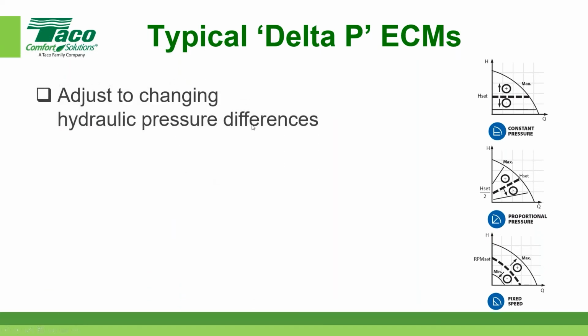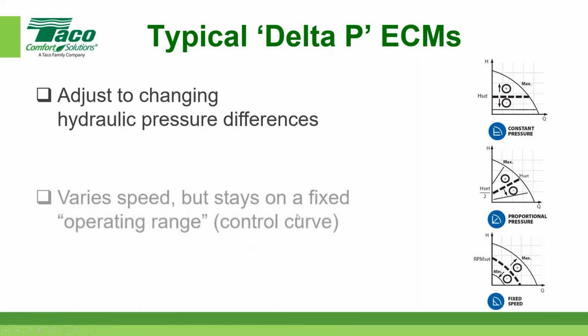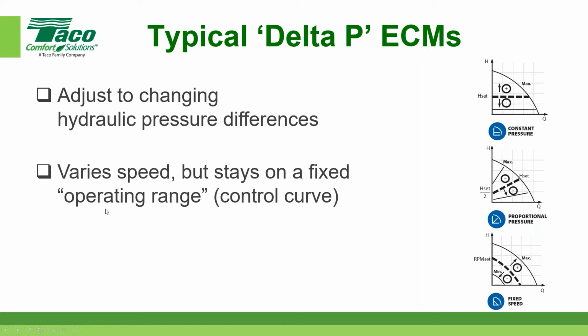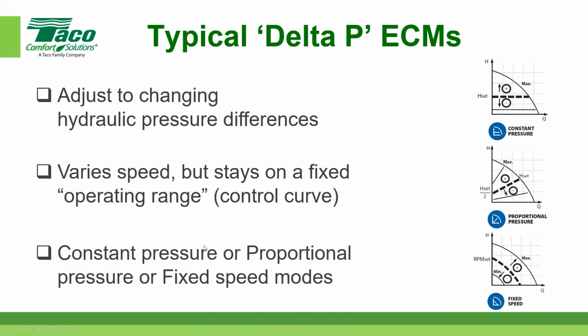So the hydraulic pressure changes of the system are what a delta P circulator uses as the input to decide what's going on and whether it needs to make a change or not. Again, I'll use that term. Some people call it control curve, but it varies its speed while staying on that operating range, depending on the information and input it receives. The three typical baseline modes of operation are constant pressure, proportional pressure, and fixed speed. And these are the little icons that go along with that.